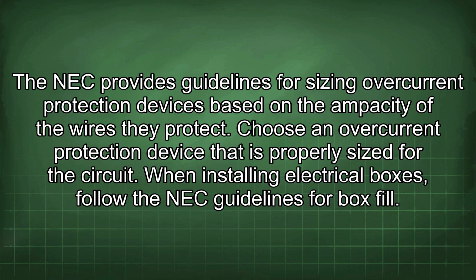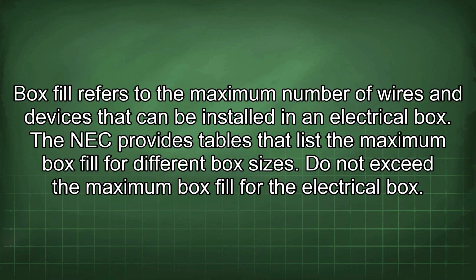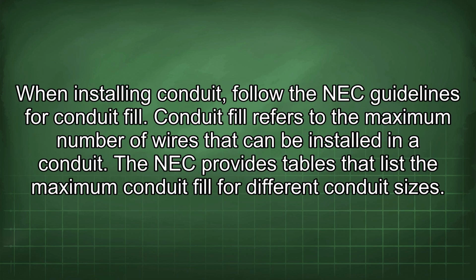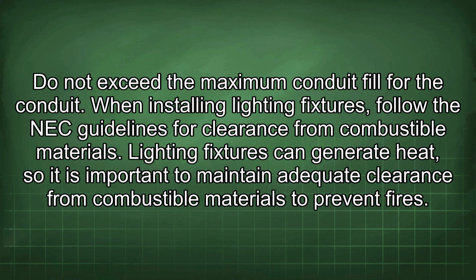When installing electrical boxes, follow the NEC guidelines for box fill. Box fill refers to the maximum number of wires and devices that can be installed in an electrical box. The NEC provides tables that list the maximum box fill for different box sizes. Do not exceed the maximum box fill for the electrical box. When installing conduit, follow the NEC guidelines for conduit fill. Conduit fill refers to the maximum number of wires that can be installed in a conduit. The NEC provides tables that list the maximum conduit fill for different conduit sizes. Do not exceed the maximum conduit fill for the conduit.